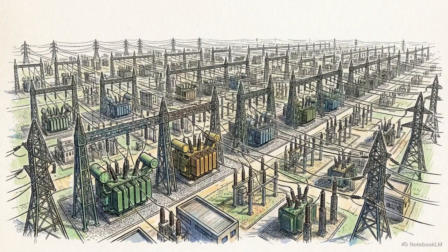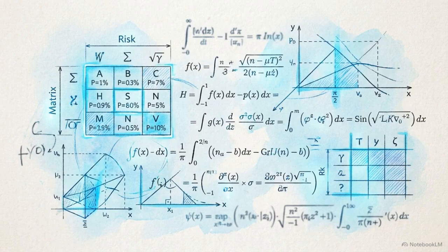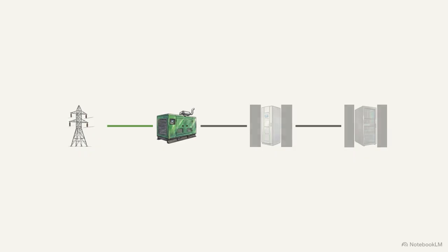Zooming out to view the entire engineered path reveals a hard truth. No matter how perfectly a single path is designed, individual components will eventually fail or require physical maintenance. To counter this, engineers use redundancy topologies. These are mathematical risk tolerance models that dictate exactly how much of the power infrastructure must be physically duplicated. This N-capacity diagram shows the baseline. A single failure causes a blackout.